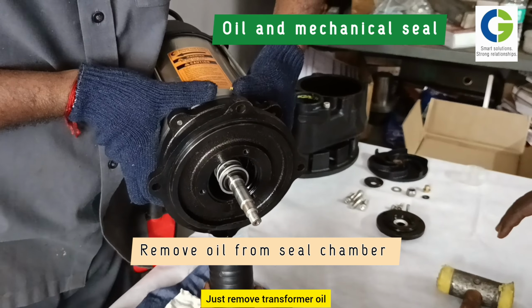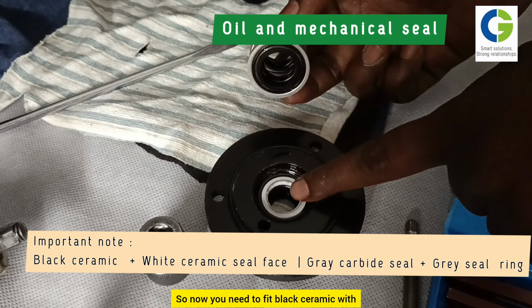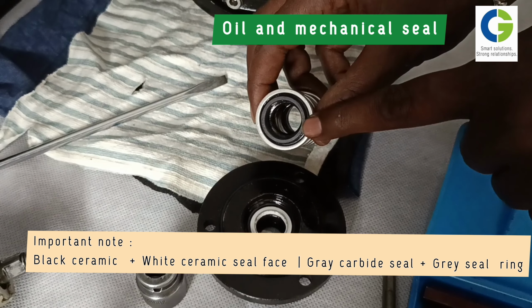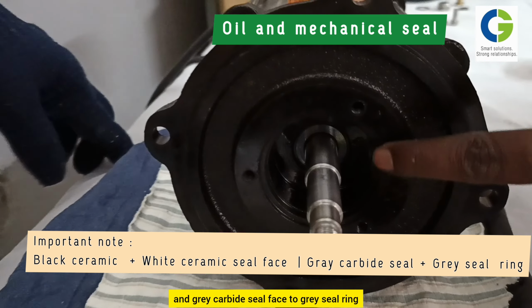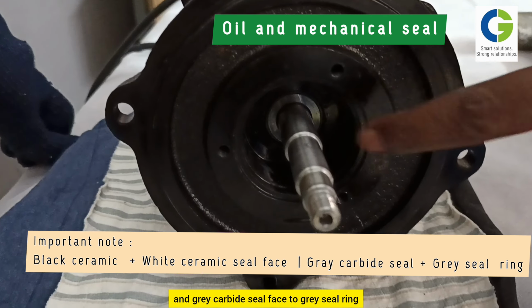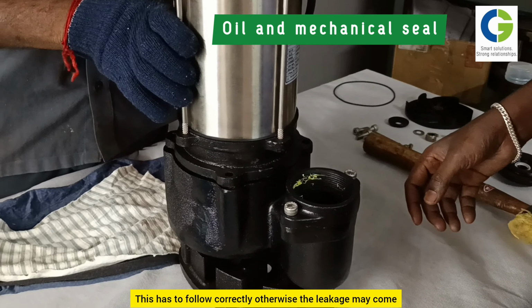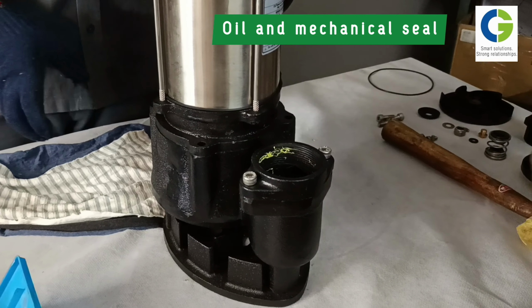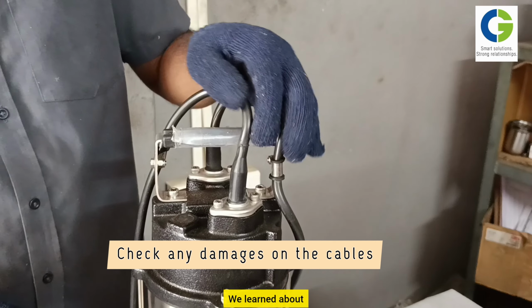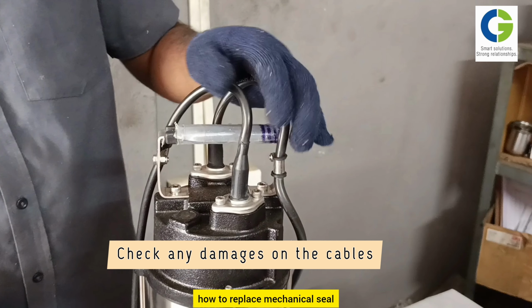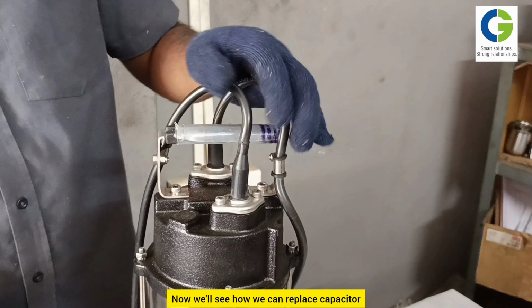Now you need to fit the black ceramic seal face with the white ceramic, and the grey carbide seal face to the grey seal ring inside where it is mounted. This has to be followed correctly, otherwise leakage may occur. We learned how to replace the mechanical seal, oil seal, and impeller. Now we'll see how we can replace the capacitor and bearings.